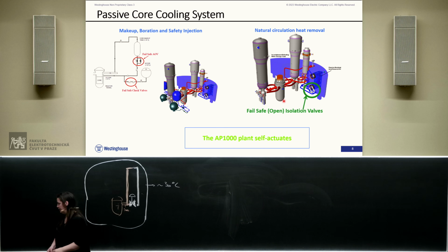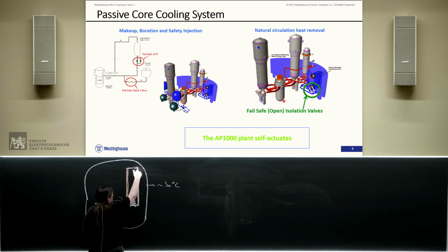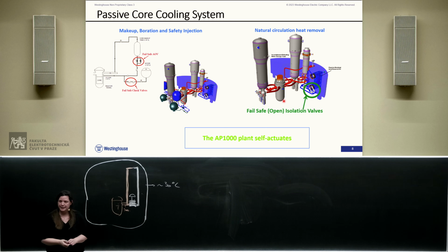And so when I have an emergency, I'm going to design my system so that this valve opens, and only the difference in density between the two columns of water is going to induce a natural circulation of the water. And so the heavier cold water will be pushed into the system. Okay?